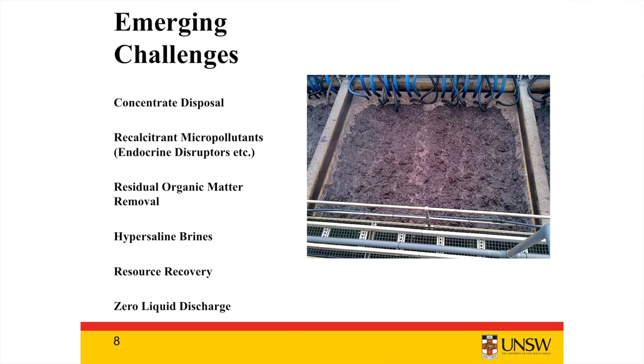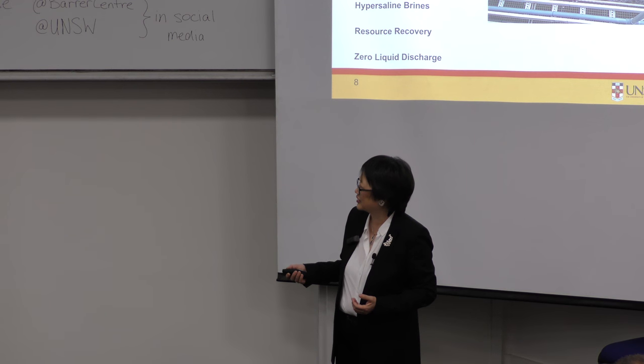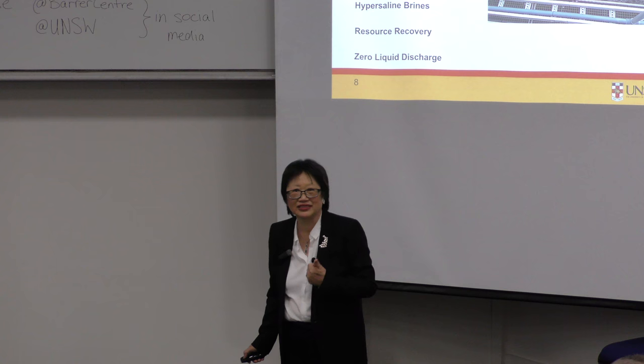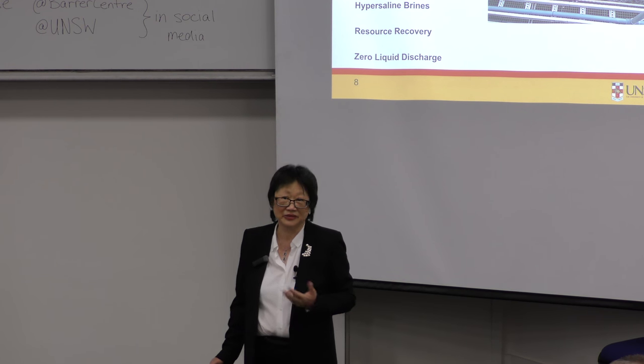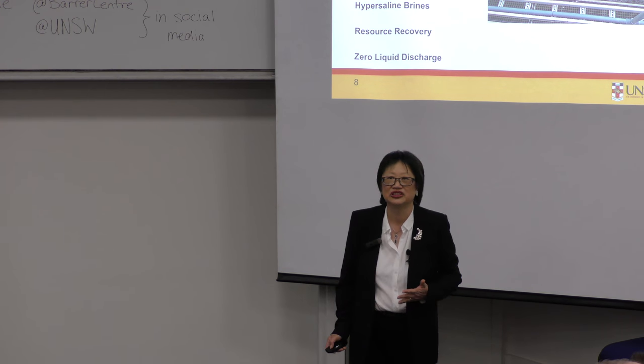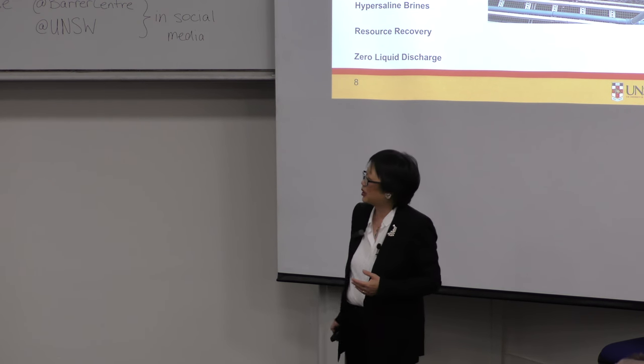The other emerging challenges, especially in water, are things I mentioned, concentrate disposal, potentially costing us as much to dispose of the concentrate of our membrane processes as to actually treat it. The recalcitrant micropollutants, as I mentioned before, and residual organic matter removal. Once you get to very small levels of organics, you still have issues with disinfection byproducts. How do you get that last bit of humic acid out without going to full reverse osmosis? I mentioned hypersaline brines, and one of the things is also resource recovery. Can we recover valuable mineral salts, such as lithium and other valuable minerals from those brines, which are environmentally sensitive? And finally, a lot of interest now in going to total zero liquid discharge. So those are some of the challenges from the water point of view.